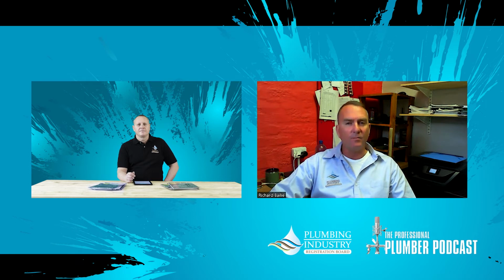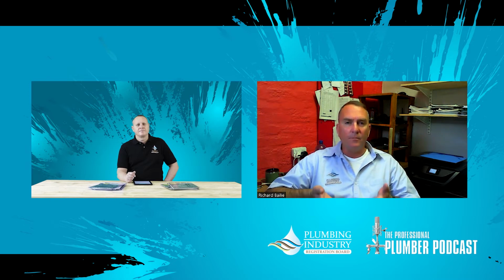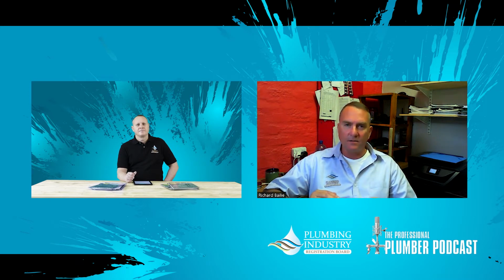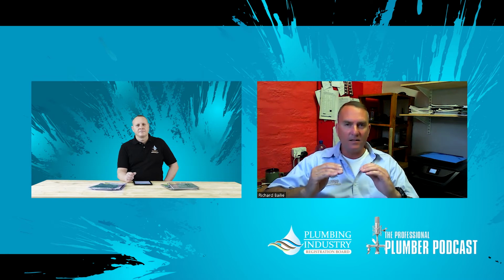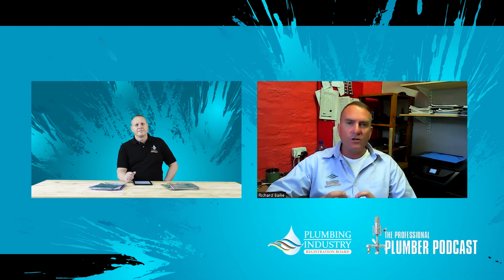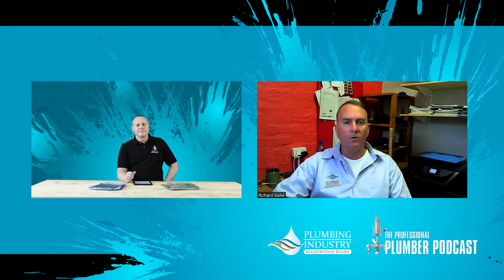Let's take an example of a 150-liter geyser. If you protect the layers within that geyser, these stratification layers, you could probably quite easily realize about 130 liters of hot water from that geyser, because you are gradually displacing the hot water, and it is not mixing, it is staying hot at the top, and eventually you'll use it and deplete it and then dip off to cold.